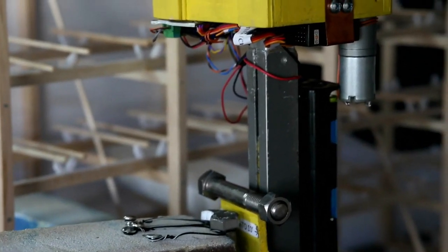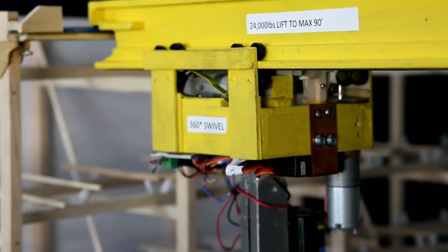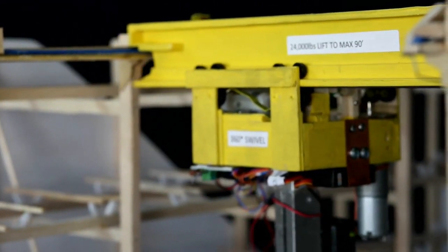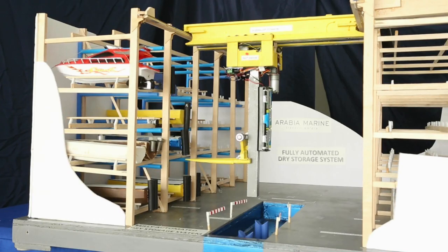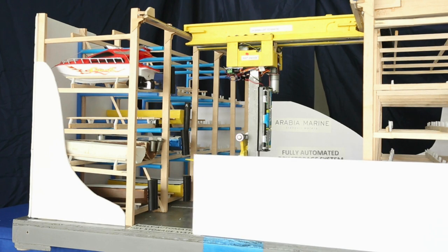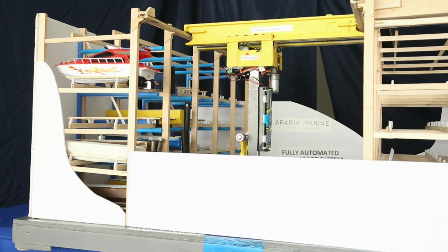Given the fire department will not enter a warehouse with a boat fire due to the danger of flaming parts falling off, the risk of damage to other boats is extremely high, as is the risk of losing the entire warehouse. The alarm system is on call to immediately close all doors and air inlets, allowing the nitrogen to quickly drop the percentage of oxygen.